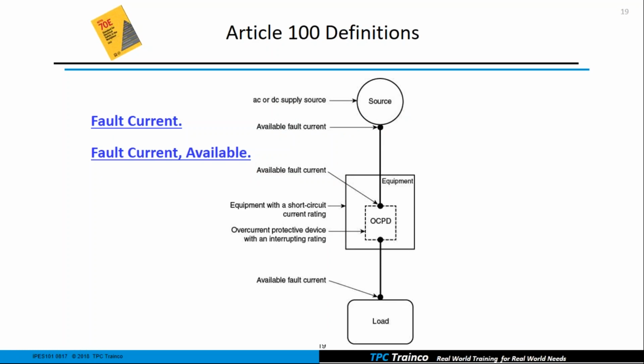It could be a photovoltaic system. It could be a generator, whatever. Fuel cells now, I notice, are becoming very popular. But then it gives us a little diagram to show us that the available fault current close to the source, of course, is probably the highest it's going to be. And then when it gets down into the equipment, it could become lower as we add impedance to that circuit.